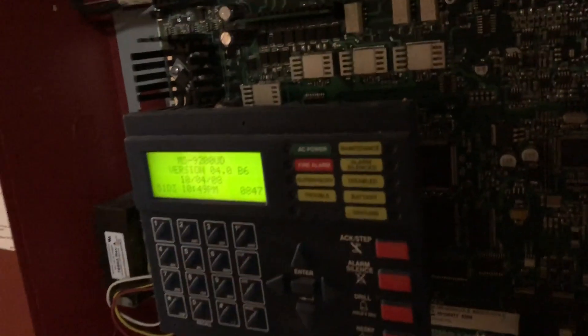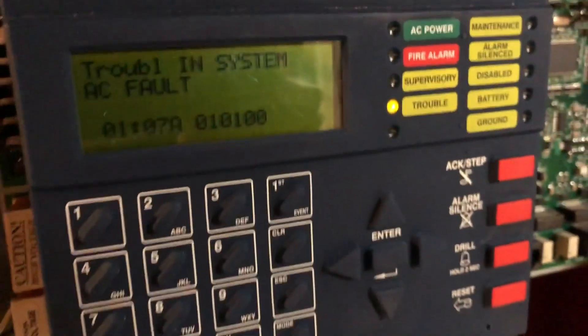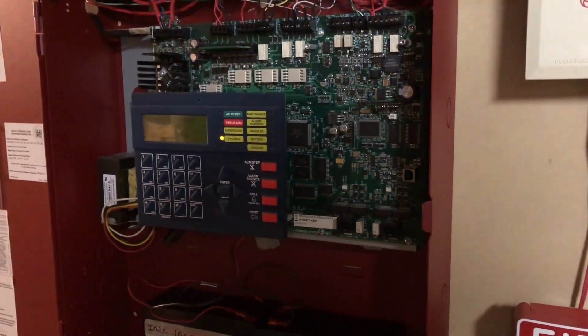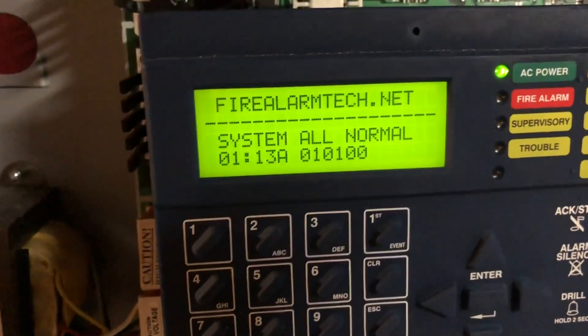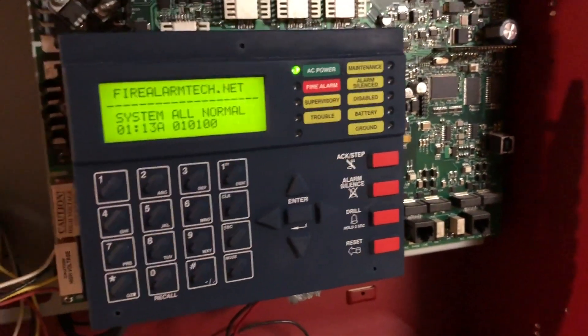So I'll put this away. Guys, that's actually going to wrap up this system for today. I have recorded the past three system tests all today. And I'm pretty sure the time and date is wrong — that's because I was trying to test this, and I'm pretty sure I almost blew up my panel. But I didn't, so that's pretty cool. Mistakes happen, shorting things out happens. Luckily, there are features in a power-limited panel that prevent that from destroying itself. And as you'll see, the panel is still functioning. I can go ahead and grab my massive cords here and plug it back in, and we'll have the power kick right back in. You can see all systems normal. Guys, that's going to wrap up the video — check out the links in the description below, go ahead and vote for devices you want to see in the next system, and I will see you all in the next video.